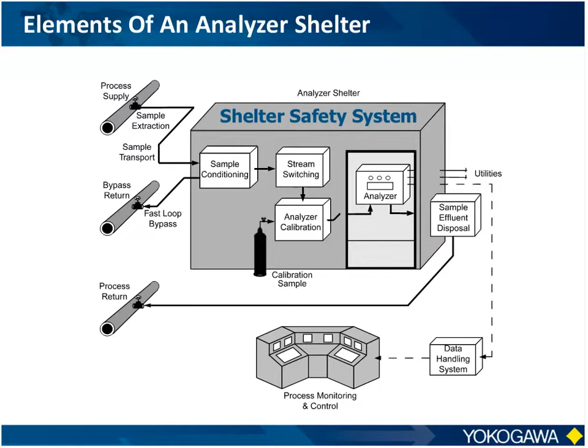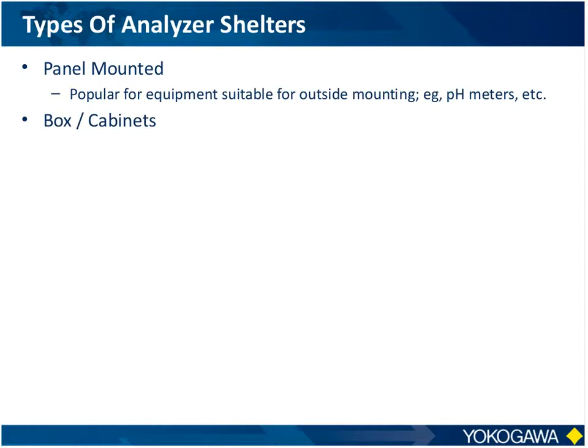The first thing you'll encounter when you deal with analyzer shelters or analyzer packages is there's quite a wide variety of packaging options available. The first is it might just be a simple panel where you take a piece of equipment such as a pH probe, mount it on a steel plate, bring all the tubing and wiring connections in, and then mount it out in the weather, perhaps with a simple sun shield. Or if it's a small analyzer all by itself, like a small oxygen analyzer, you might just put it in a small box or perhaps a freestanding cabinet for something like a CEMS package. This is perfect for small applications.